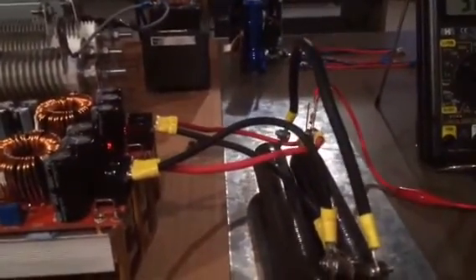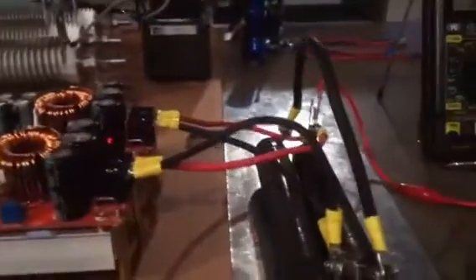So you can adjust the outputs independently, get them exactly the same, and then use the same gauge wire, the same length wire, the same terminations to your load. This is also important, but it's probably not going to address the load sharing problem completely. Let's take a look at that. All the terminations are exactly the same. Wire lengths, gauges, everything is identical here, both on the input side, which is less critical in this case, and the output side.